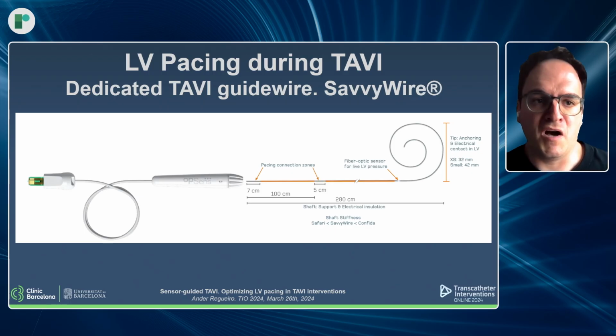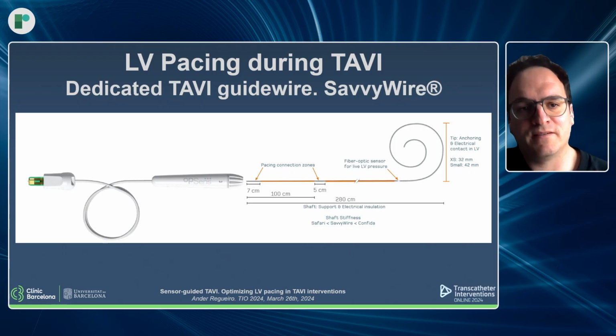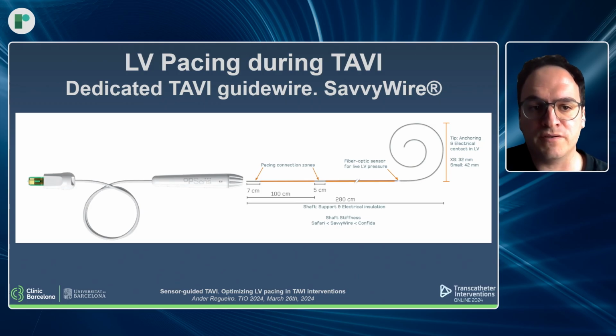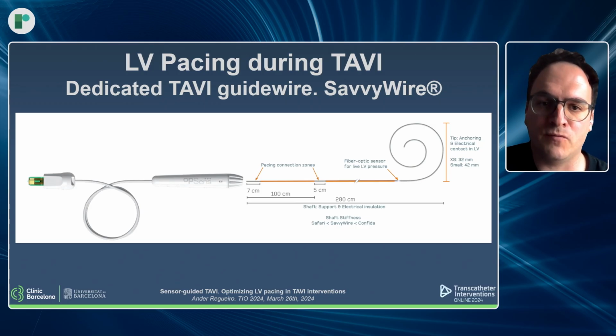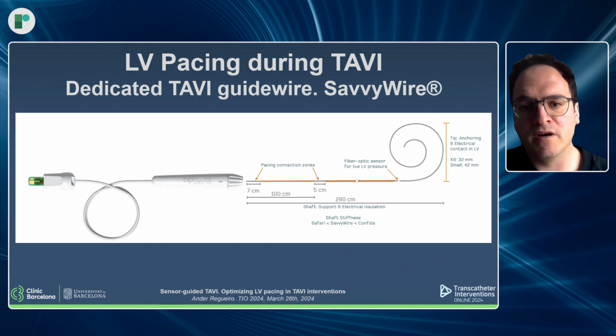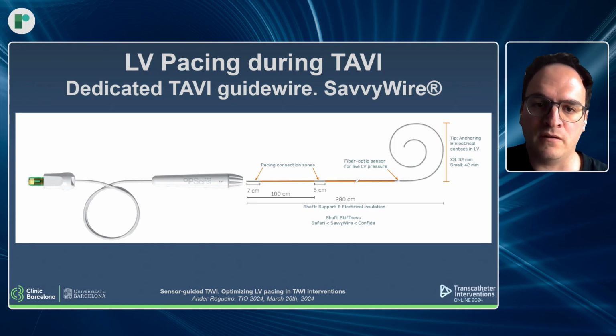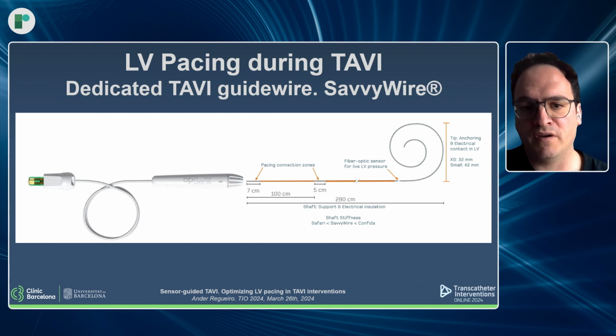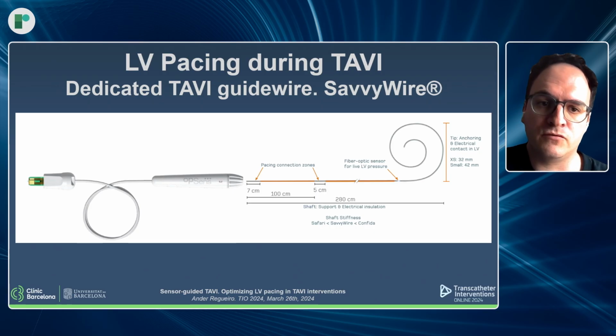And moving on, we now have a wire that is specifically dedicated to do this. So this is a dedicated TAVI wire, the SavvyWire, which is a pre-shaped wire used to deliver the TAVI, that has also 2 other characteristics. The first one is that this wire has an electrical isolation. As you can see, the orange part of the wire, just after the end of the shape of the curve of the wire. And it has 2 spots to put the pacemaker battery to do pacing through the wire.